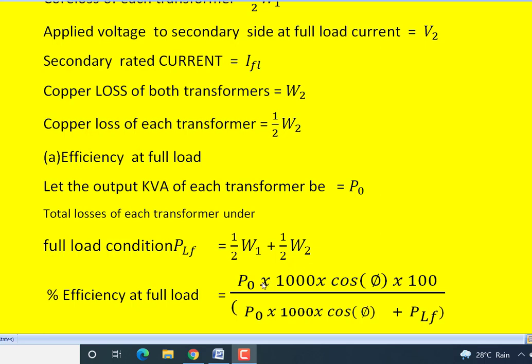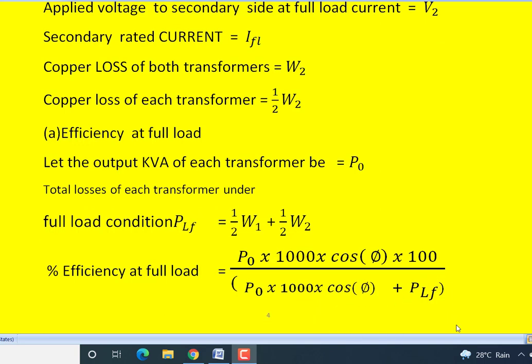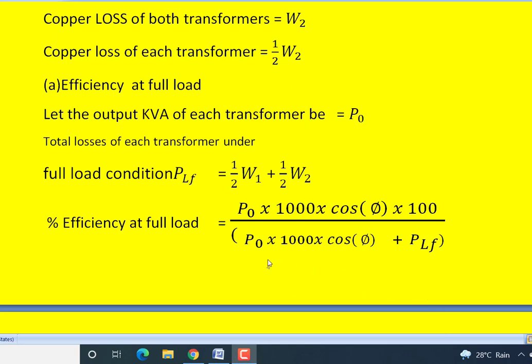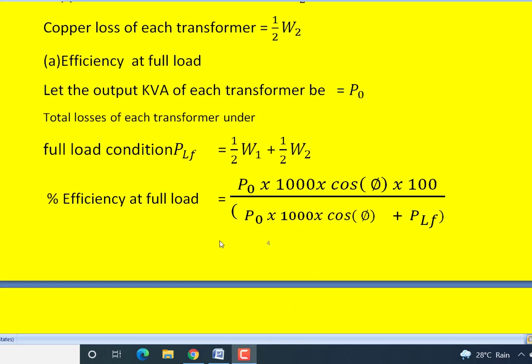So this VI is nothing but the kVA, that is P naught, and because W1 and W2 are in watts, we have to convert this P naught into watts. So we multiply with 1000 into cos phi into 100. This 100 is used to get the percentage of efficiency. So divided by output plus total losses. The output, to repeat, is P naught into 1000 into cos phi, plus PLF. Then we get the efficiency of each transformer at full load condition.